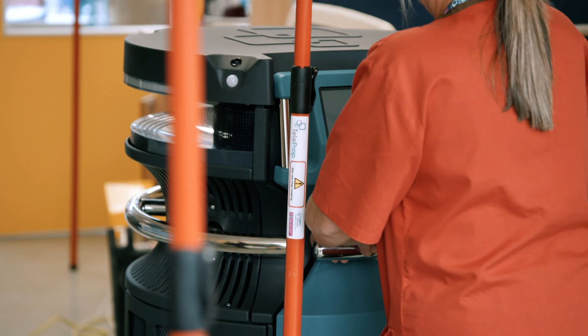We have to be outside because the environment inside we're going to fill with hydrogen peroxide vapour, which will kill the microorganisms. The bleach vapour is so strong it can't be allowed to leak out, so all the air vents are sealed and covered so the gas doesn't harm people elsewhere in the hospital. We seal the room up completely with tape on the door, then make sure everything's ready before we start.